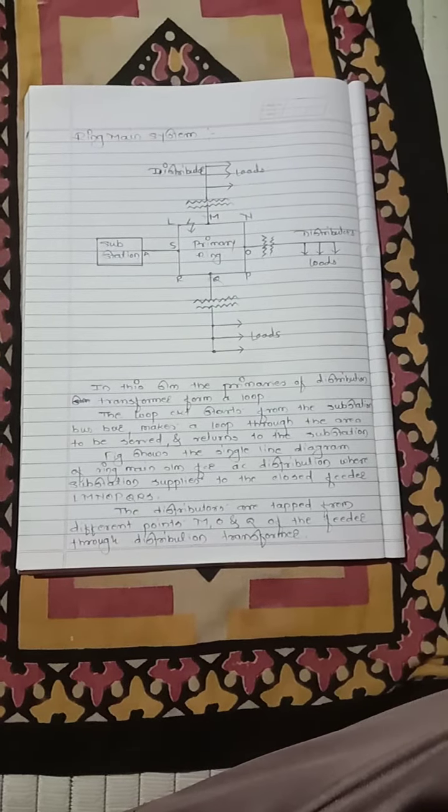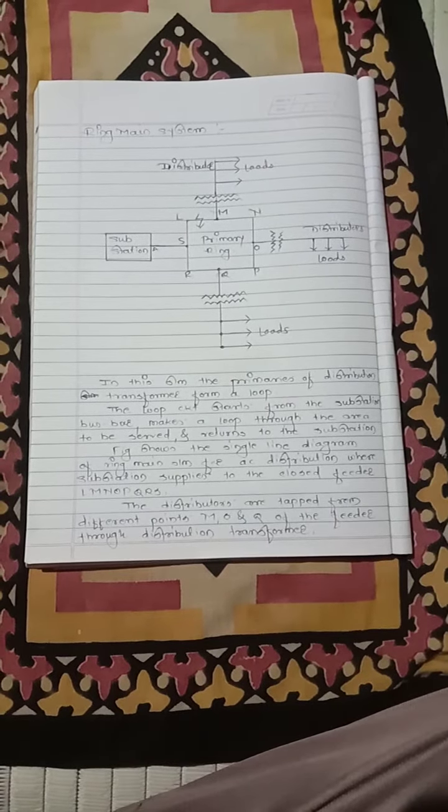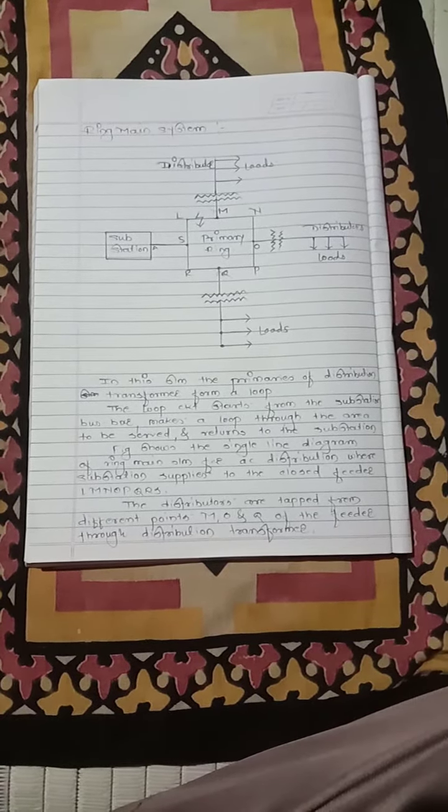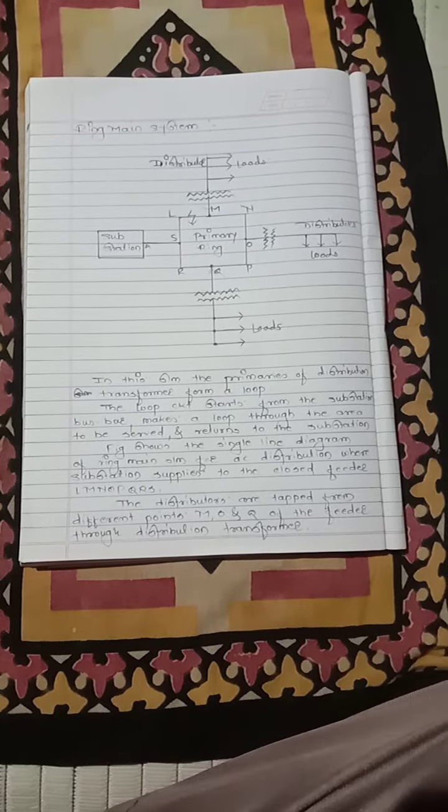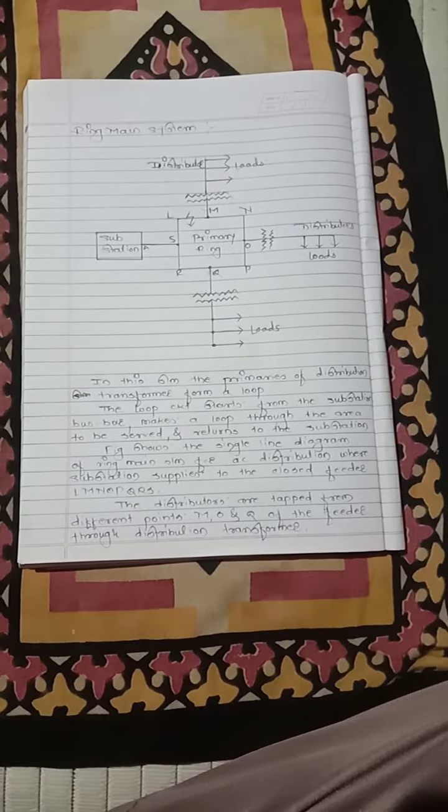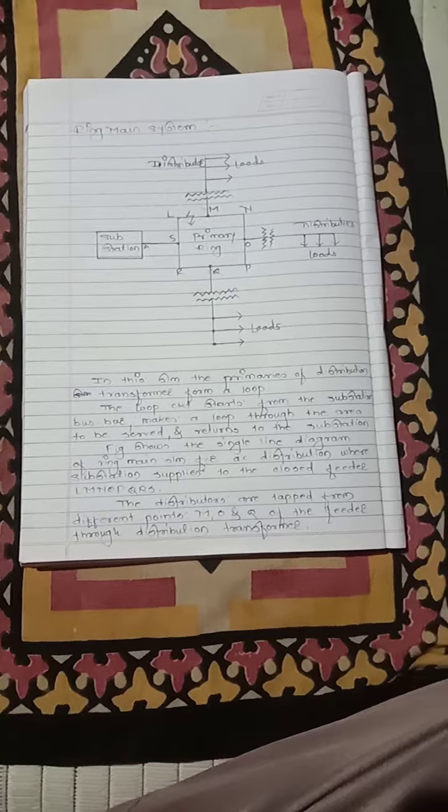Suppose a fault occurs at point F in section SLM of the feeder. Then section SLM can be isolated for repairs, and at the same time, the continuity of supply is maintained to all consumers via the alternate feeder path S R Q P O N M.